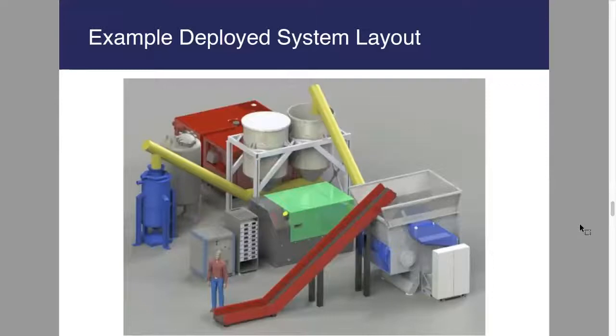Through our high impact project grant with NREL, we've been working with NREL, Perkins, and Woodward Controls to design a modified diesel genset that will use our syngas as fuel. In addition, along with Priori, we've been designing a properly scaled filtering and scrubbing system to clean the syngas of chlorine or sulfur that might be in the feedstock before introducing it into the genset. For illustrative purposes, this design requires a footprint of about 50 feet by 40 feet, or about 2,000 square feet, with a height of around 10 feet.